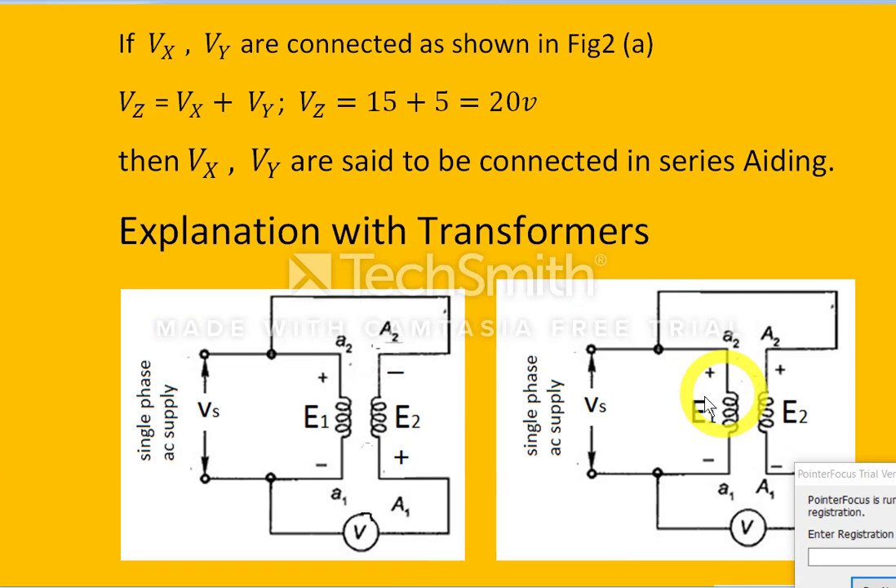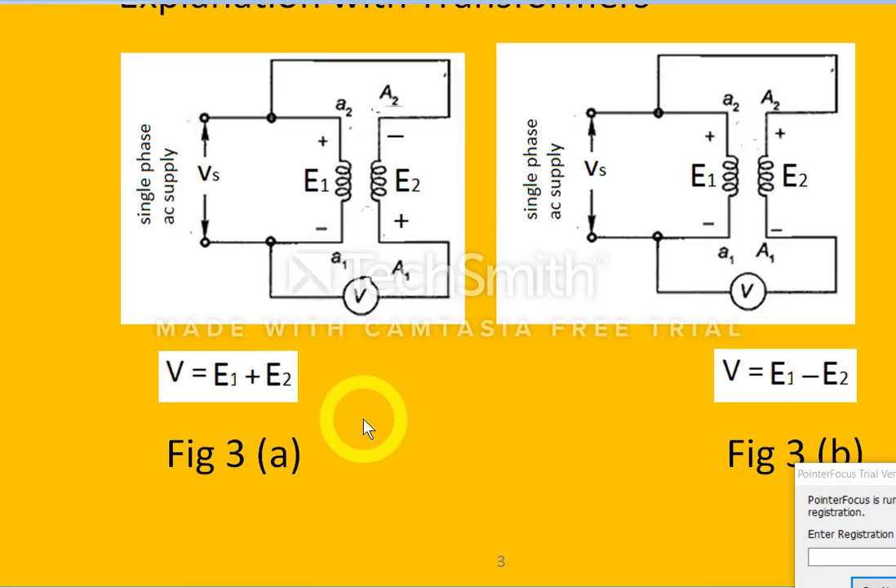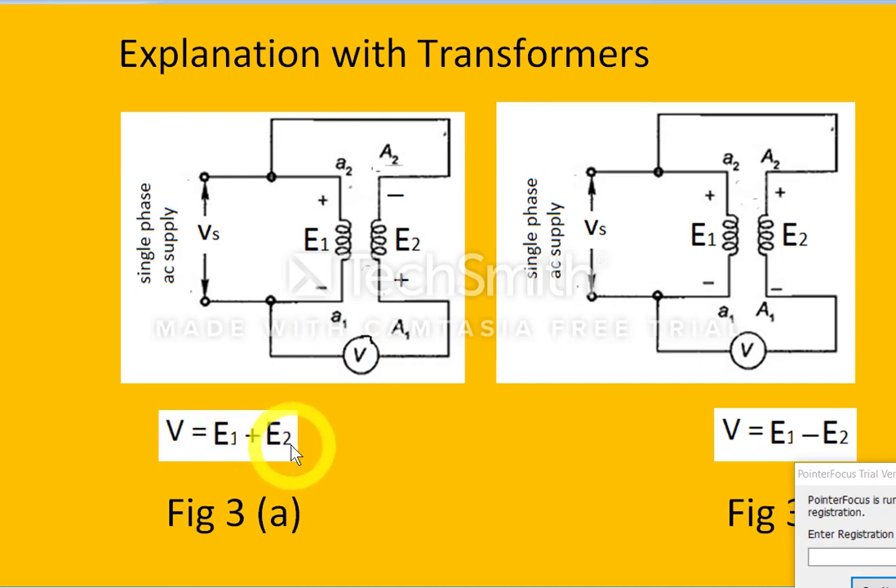The same transformer is represented in a circuit diagram. A single-phase AC supply Vs is connected to the primary winding. Terminals a2 and A2 are connected together, while a1 and A1 are connected via a voltmeter. E1 is the induced EMF in the primary winding and E2 is the secondary induced EMF. With the polarities shown, E1 and E2 are connected in series aiding, so the voltmeter reading equals E1 plus E2.